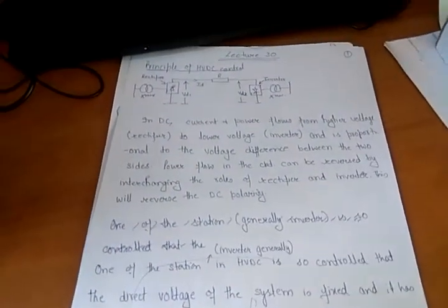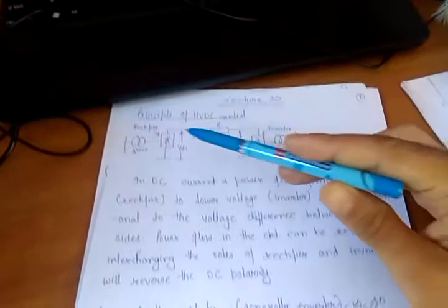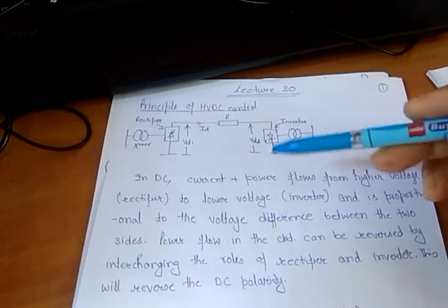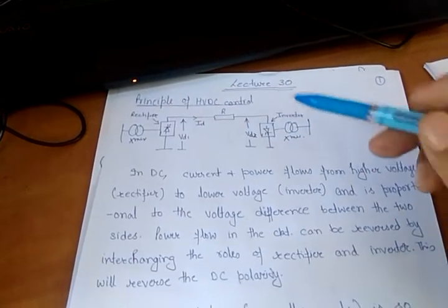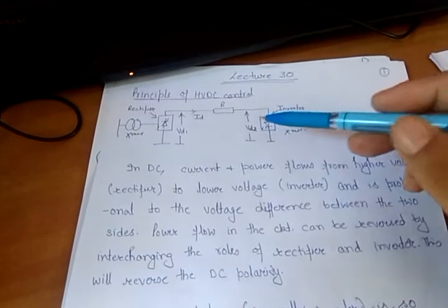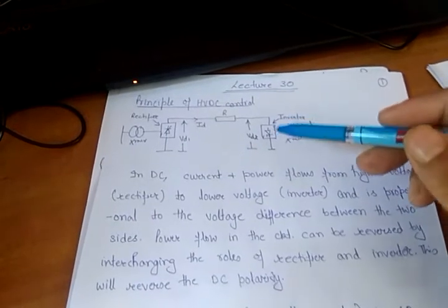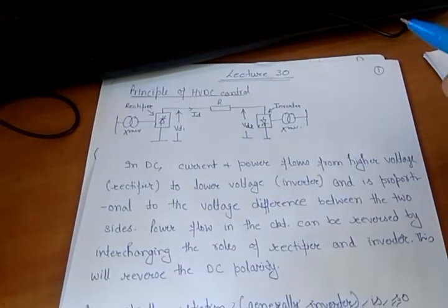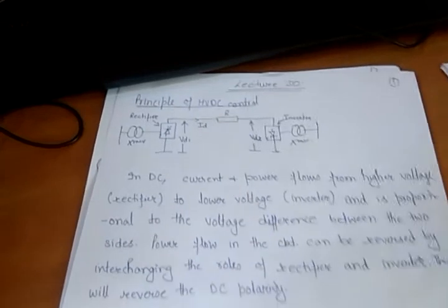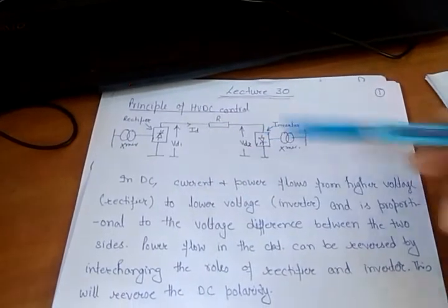Continuing lecture number 30 - we have two stations: one acts as inverter, the other acts as rectifier, and power flows from rectifier to inverter. If you want the power flow to reverse, you interchange the roles of the inverter and the rectifier. The rectifier will act like an inverter and the inverter will act like the rectifier, and only in that case the direction of power flow will reverse.